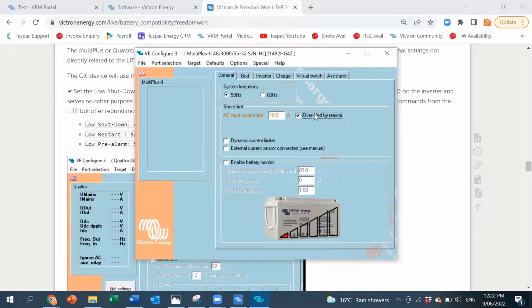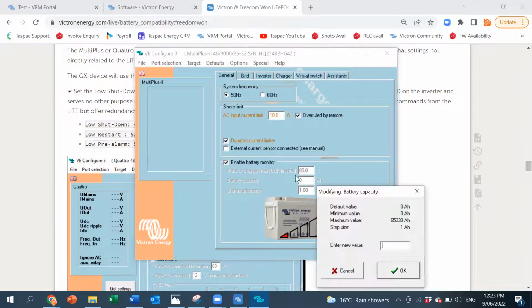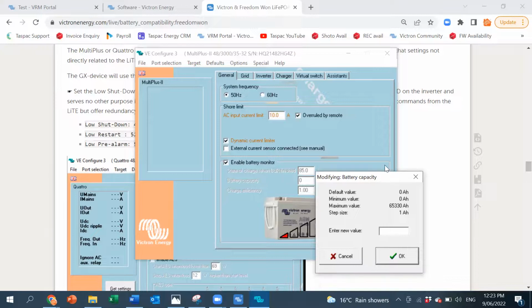Now, overruled by remote basically means if that's ticked, then you can actually overrule this. You can change this 10 amp rating to anything you like using the remote console. And I'll show you how to do that later. Dynamic current limiter basically means that the inverter will try and limit the current and bring it up nice and slow, be really gentle on the generator. External current sensor connected, we don't really need that unless you're using energy meter and you're connected to the grid. So that's unticked, and we enable the battery monitor and we say what's the battery capacity in amp hours.